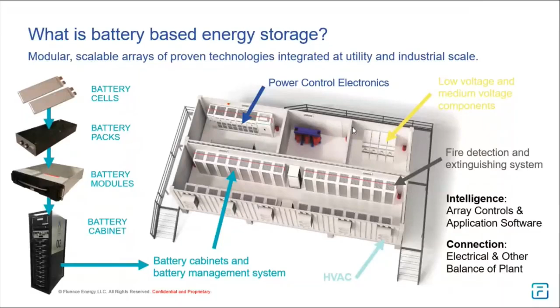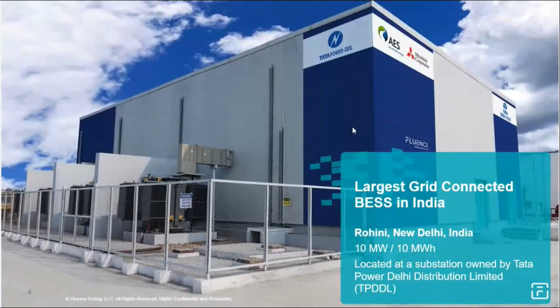All of that together, when dispatched or charged in a predictable, safe manner, makes up what we call a battery storage resource. Having said that, Fluence has deployed a 10 megawatt, 1 hour battery storage system in New Delhi. It's in northern Delhi, in the service area of Tata Power Delhi Distribution Limited, which is a distribution utility for the northern part of Delhi. What you're looking at is a battery storage system enclosed inside a civil structure - so this is actually a building. What you see on the left are the 4 transformers, each a 2.5 MVA transformer. The 4 of them add up to give you 10 MVA, and the duration is 1 hour.